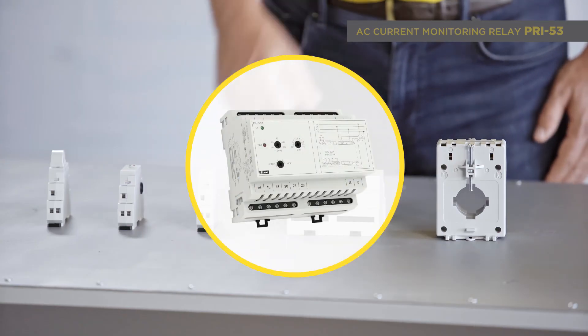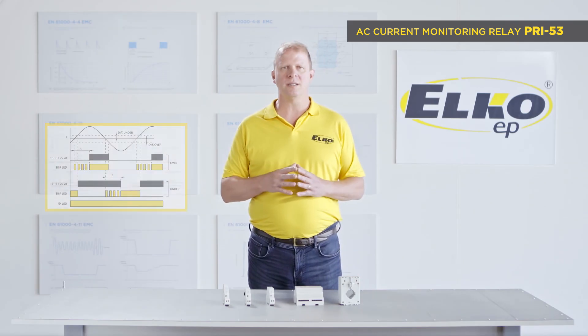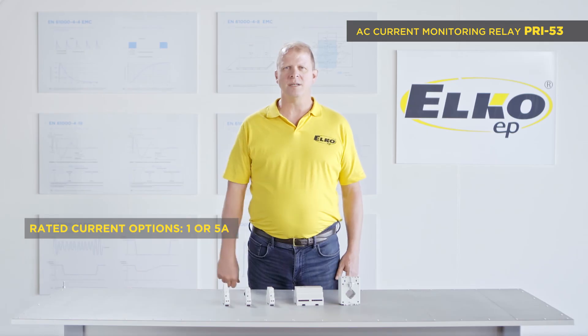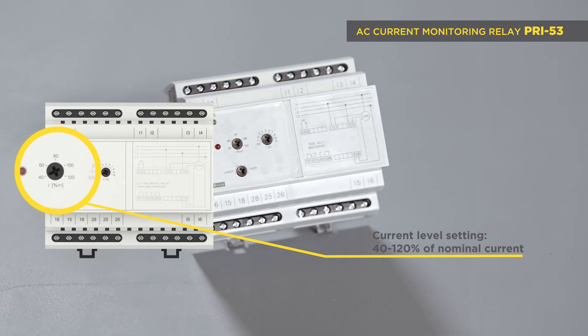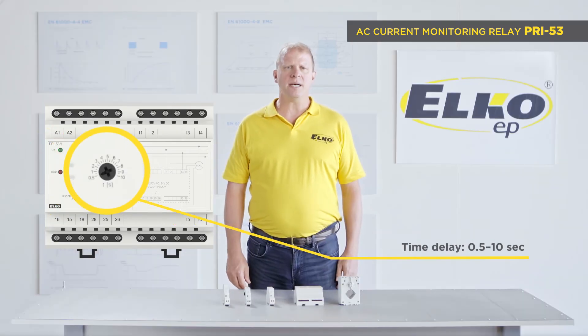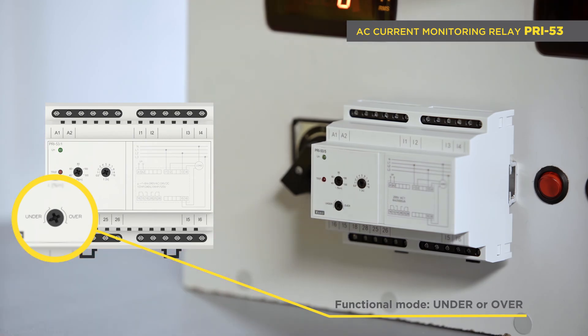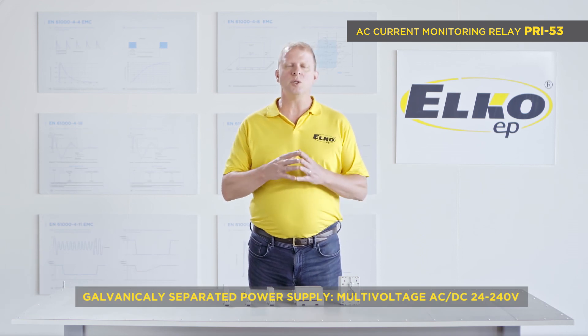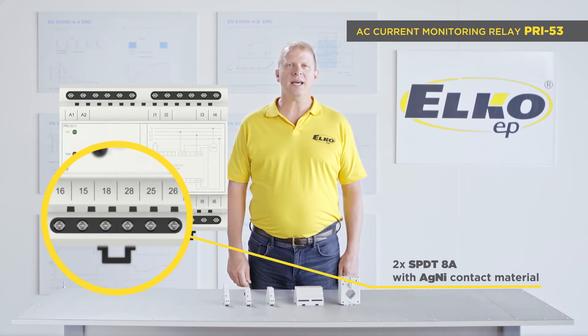PRI 53 is intended for alternating current measuring in a three-phase network via built-in shunts. It is available in two options according to the current range: 1 and 5 amps. The current level is adjustable by potentiometer in a range of 40 to 120% of the nominal current. It has an adjustable time delay of 0.5 to 10 seconds for eliminating peaks. The functional mode — under or over — is set by a switch on the front panel. The supply voltage is galvanically separated from monitoring inputs in a multi-voltage range of 24 to 240 volts AC/DC. There are two output relays with an SPDT 8 amp changeover contact.